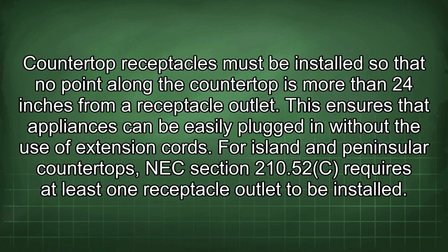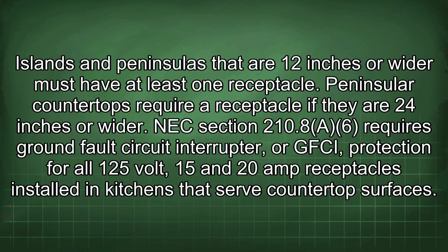For island and peninsula countertops, NEC section 210.52(C) requires at least one receptacle outlet to be installed. Islands and peninsulas that are 12 inches or wider must have at least one receptacle. Peninsular countertops require a receptacle if they are 24 inches or wider.